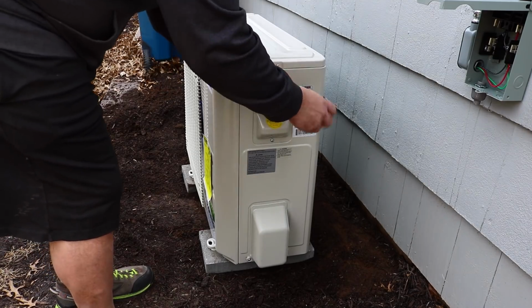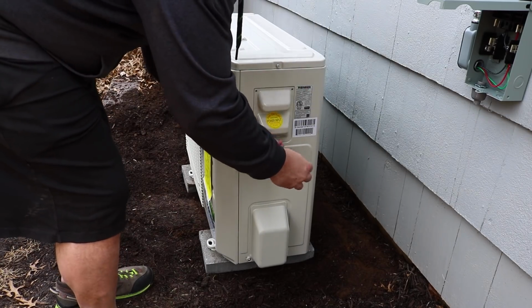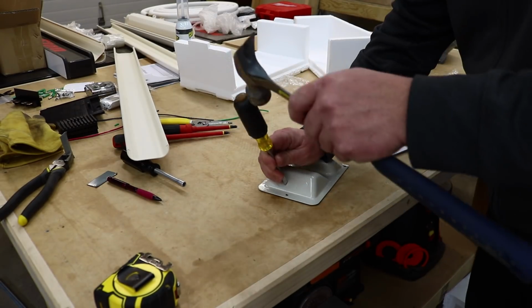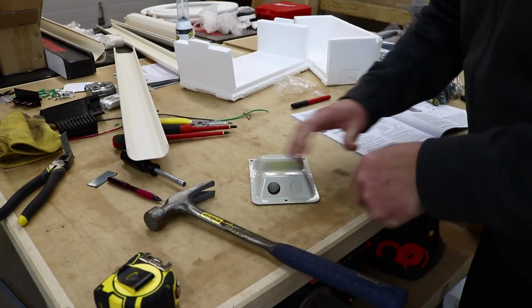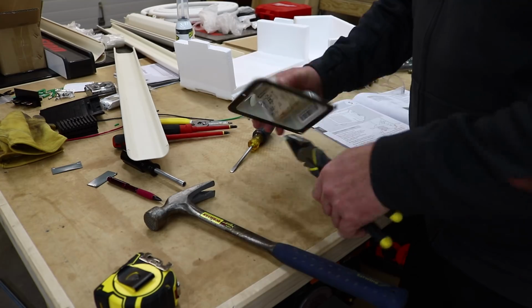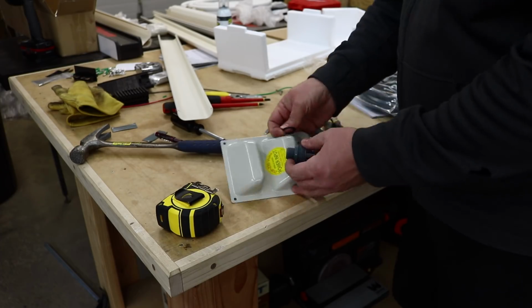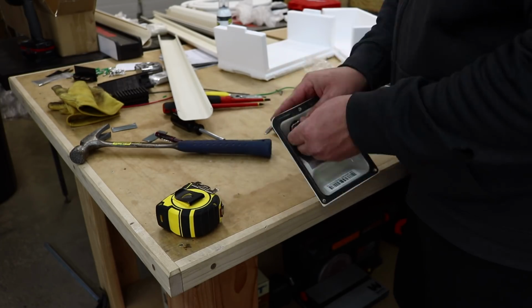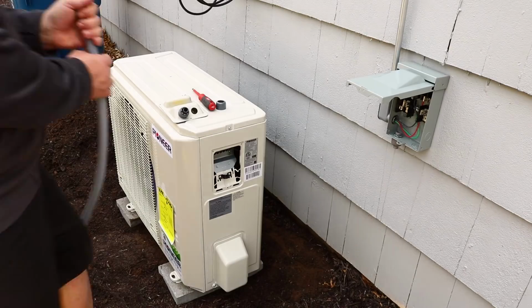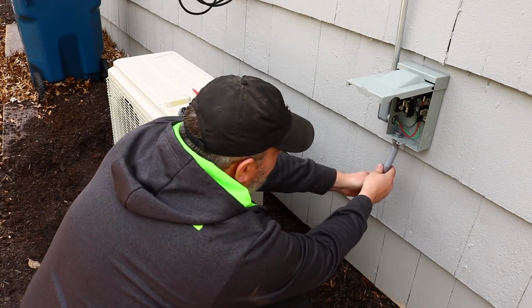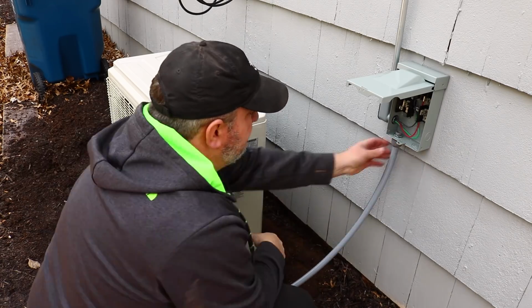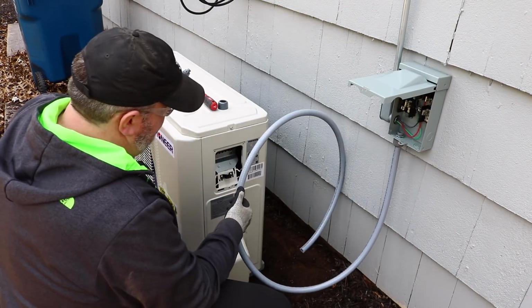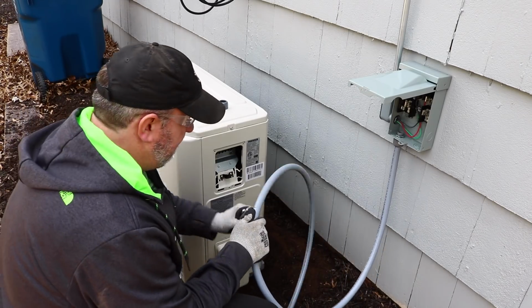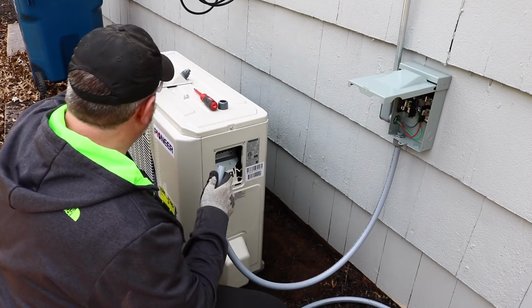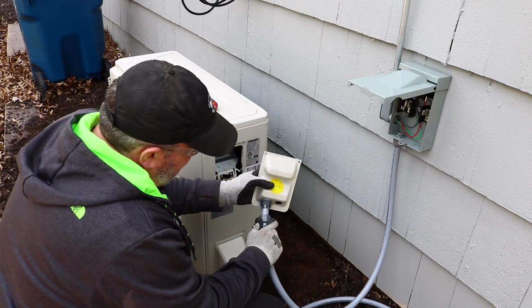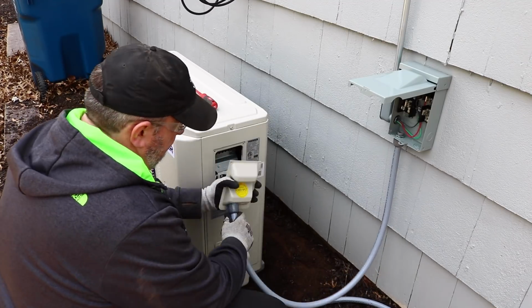I then needed to make the connection between the disconnect panel and the outdoor unit, so I removed the terminal cover from the outdoor unit and punched out 2 of the knockouts. To make the run from the disconnect box to the outdoor unit, I bought some liquid tight conduit, which comes with compression connectors. I connected one to the disconnect box and then attached the liquid tight and cut it to the length I needed to make the connection to the outdoor unit. I then connected the outdoor unit's terminal cover to the liquid tight in a similar fashion.